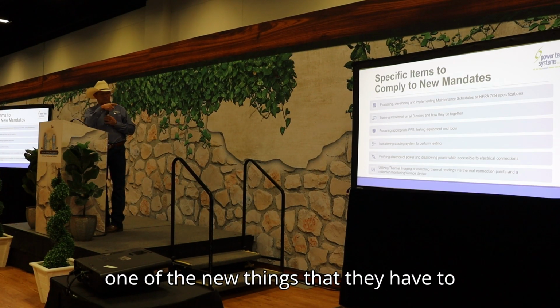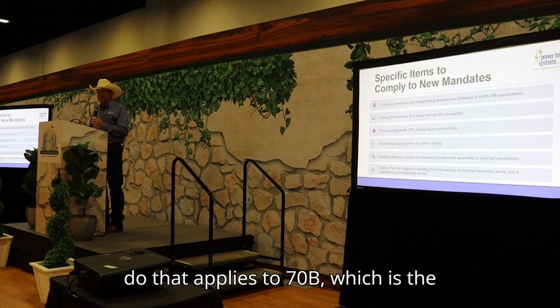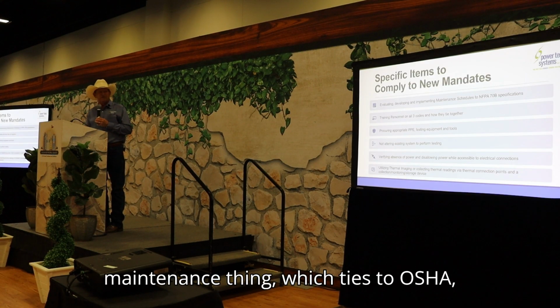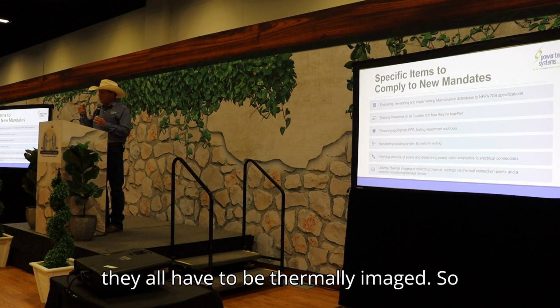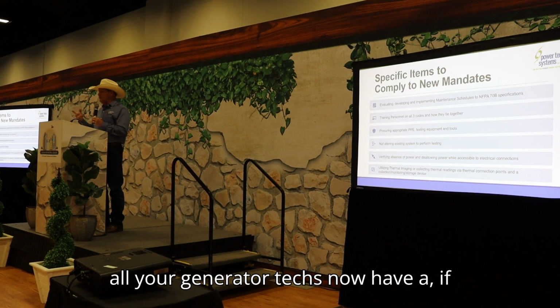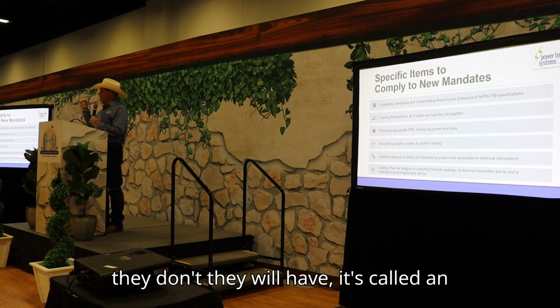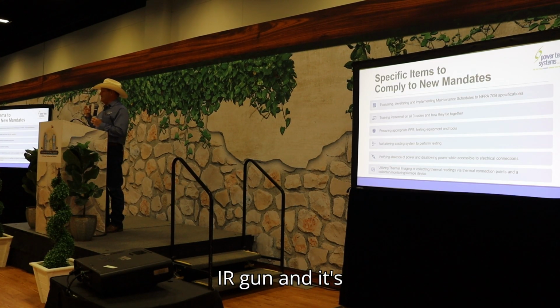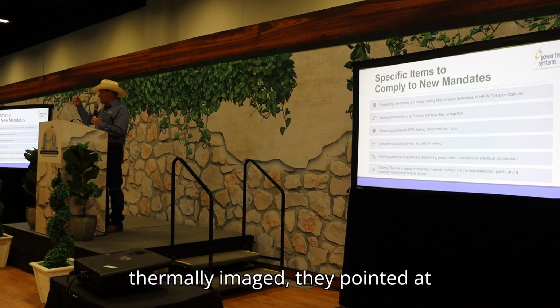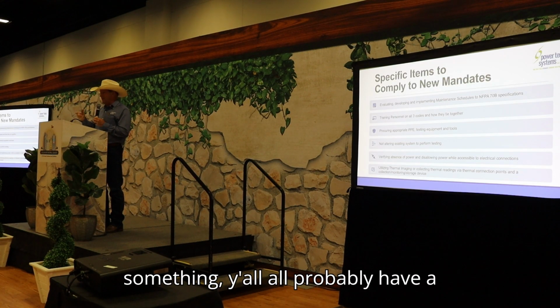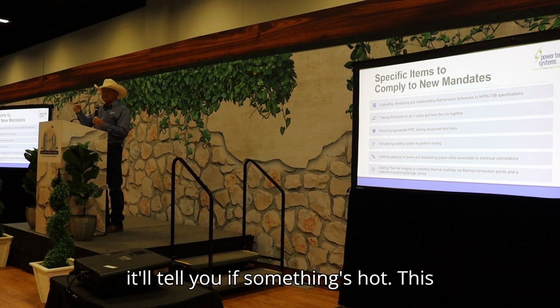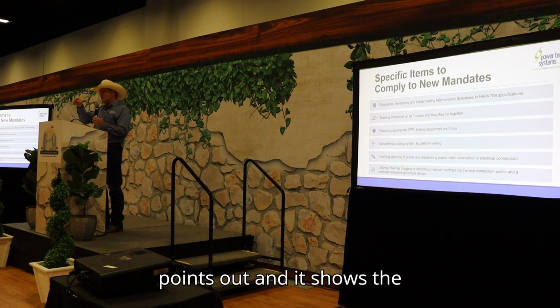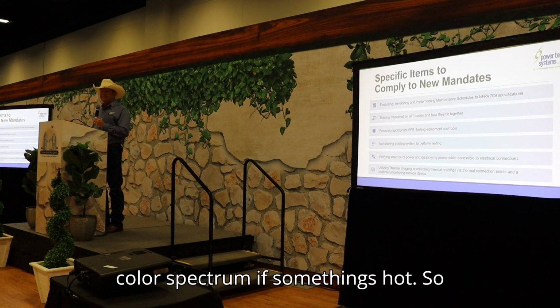So one of the new things they have to do that applies to 70B, the maintenance code, which ties to OSHA, is they all have to be thermally imaged. So all your generator techs now have, or will have, what's called an IR gun for thermal imaging. They point it at something—y'all probably have a little thing you point in the house that tells you if something's hot. This points at it and shows the color spectrum of what's hot.